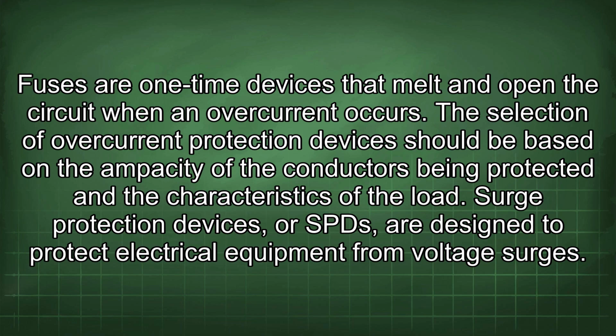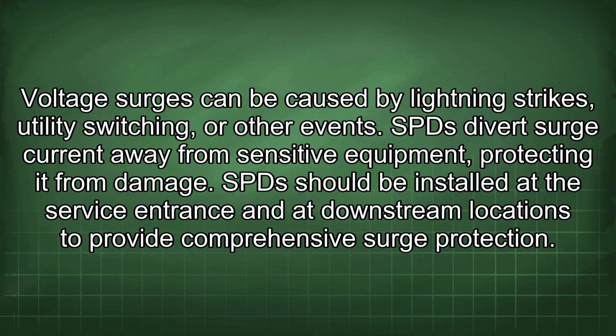Surge protection devices, or SPDs, are designed to protect electrical equipment from voltage surges. Voltage surges can be caused by lightning strikes, utility switching, or other events. An SPD diverts surge current away from sensitive equipment, protecting it from damage. SPDs should be installed at the service entrance and at downstream locations to provide comprehensive surge protection.